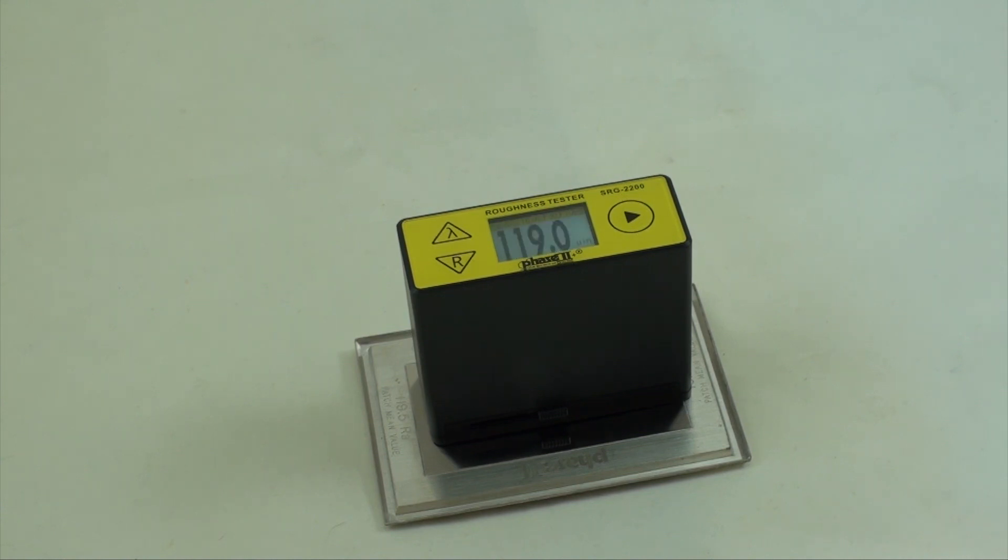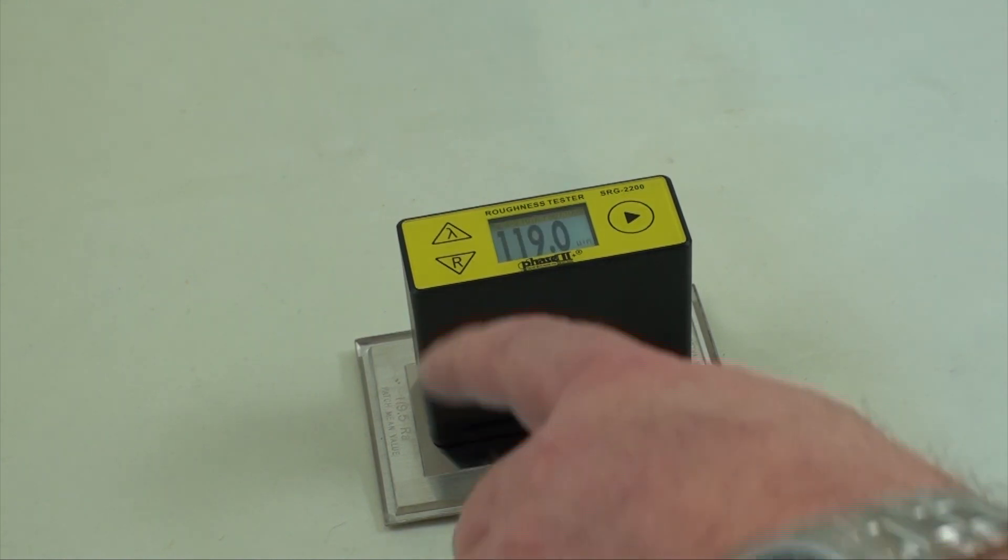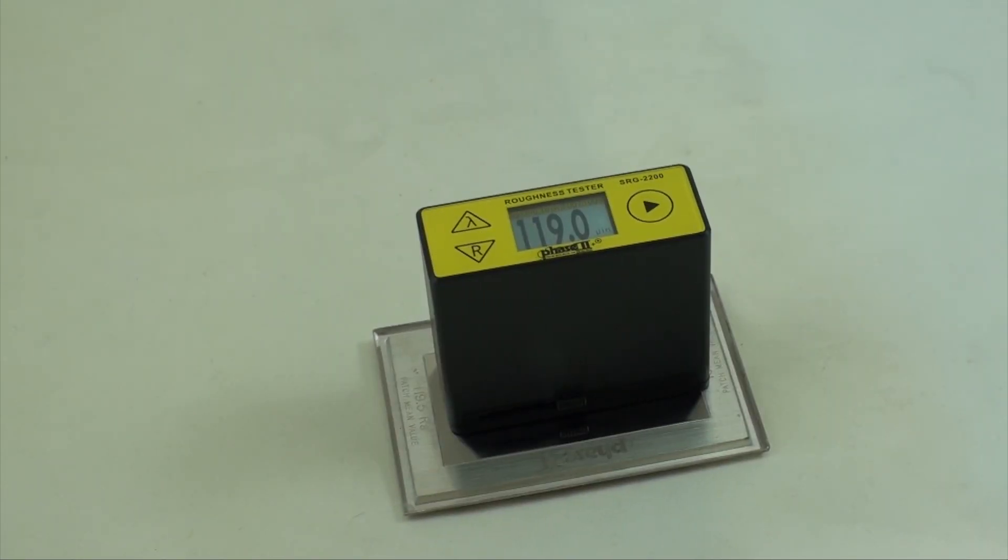Set your parameter setting or roughness scale to be used by pressing the R button. Set your cutoff length using the lambda button.